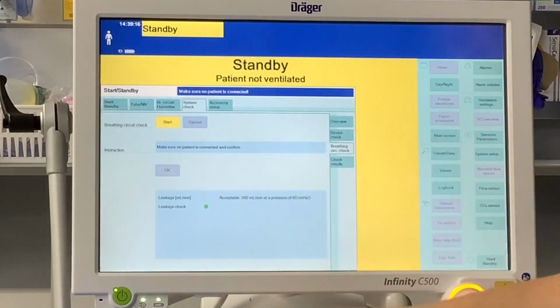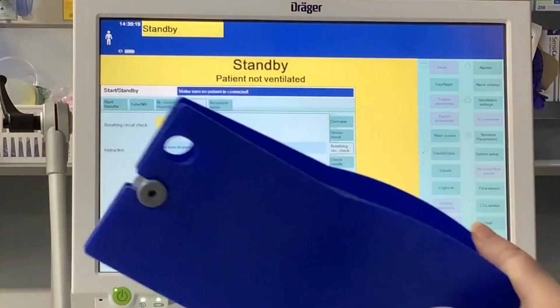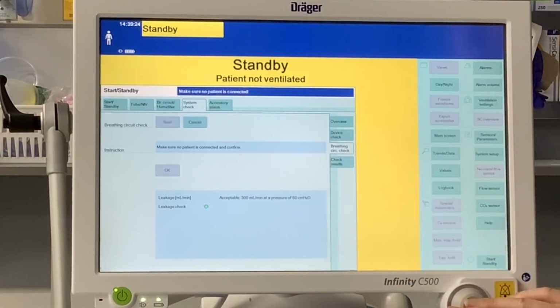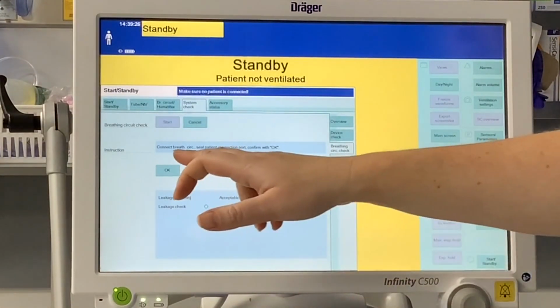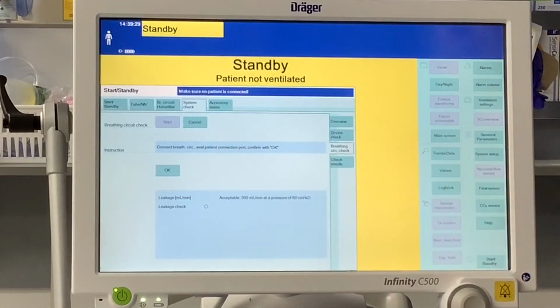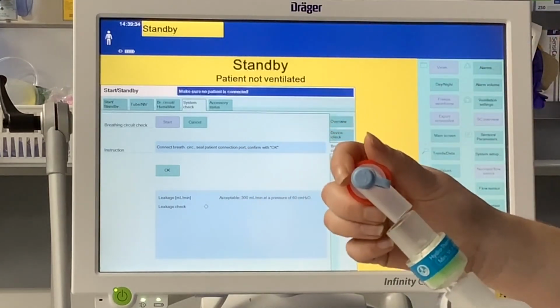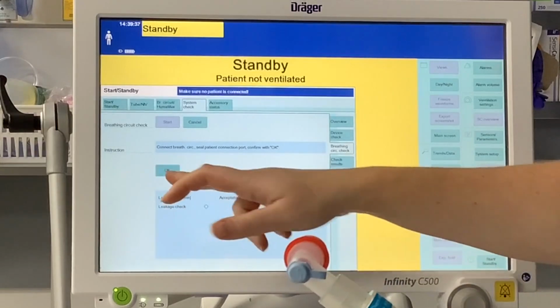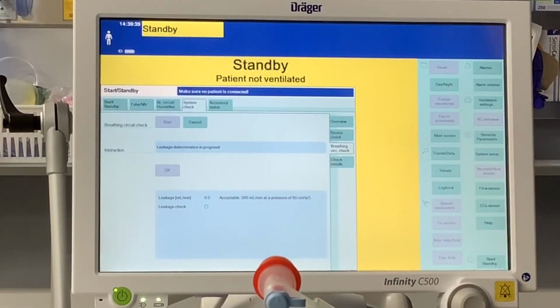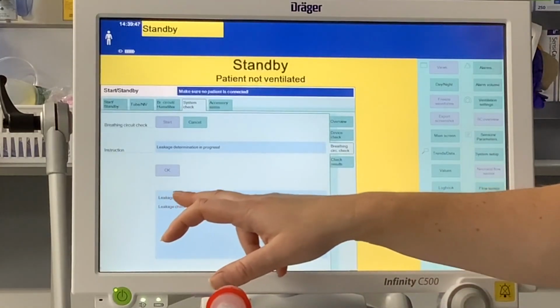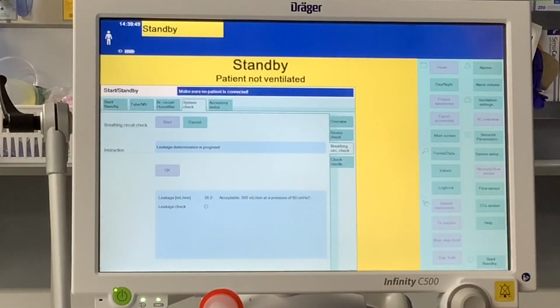It's going to say make sure no patient is connected and confirm. That means I can't have my test lung connected. So I'm going to press start. It's going to say connect breathing circuit, seal patient connection port, and confirm with OK. That's where I'm going to use this, and it's sealing it with the red cap. Press OK. If we had a leak in our circuit, this is where it's going to show up. Here it's saying leakage, and it'll always have a small amount of leak.